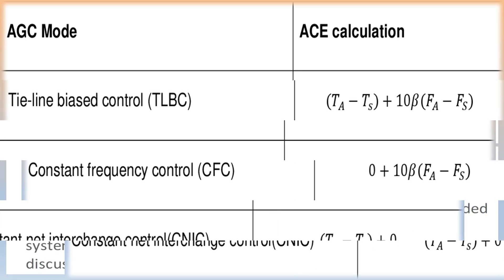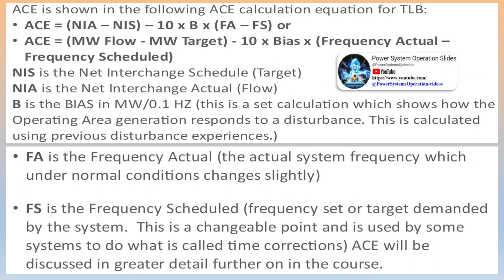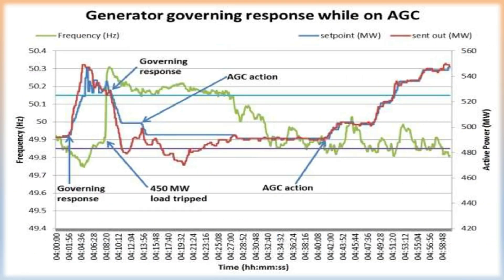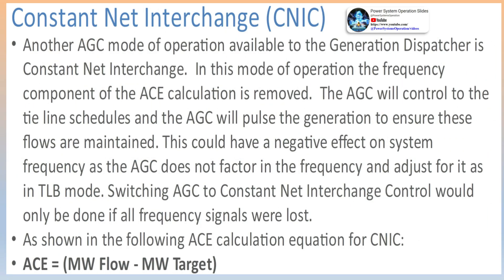ACE flow diagrams for disturbance conditions: the following diagrams illustrate the ACE calculations. If the frequency in the interconnection is low and the actual net interchange for an operating area is higher than scheduled, the two terms in the equation will tend to cancel each other out. This will indicate a disturbance took place in another operating area. Any attempts to lower the generation in this operating area to correct the net interchange deviation will have a negative impact on the system frequency problem in the main grid. If a generating unit trips anywhere in an interconnected system, the frequency decays. All the generating unit governors respond immediately by increasing their output to stabilize frequency.